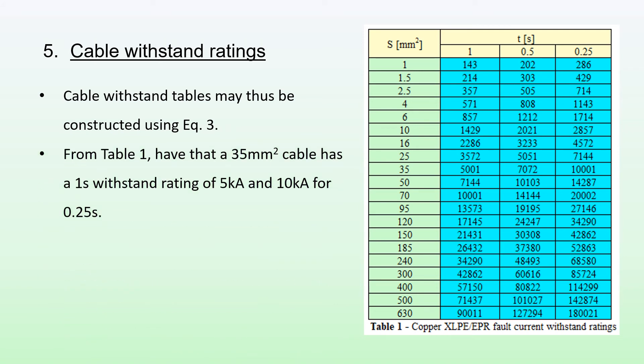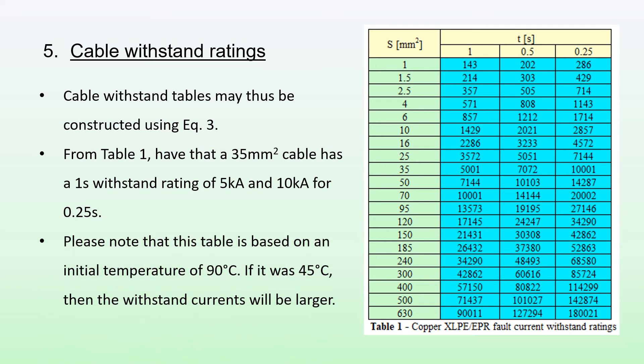For example, from Table 1, have that a 35 millimeter squared cable has a 1 second withstand rating of about 5 kA and a 0.25 second withstand rating of around 10 kA. Please note that this table is based also on an initial temperature of 90 degrees, so if I use an initial temperature of say 45 degrees, then the withstand currents of course would be larger.